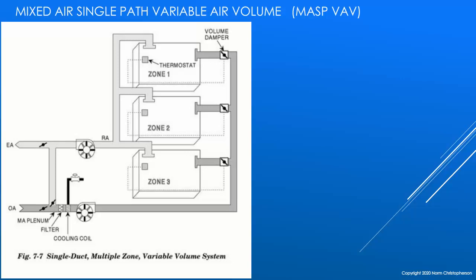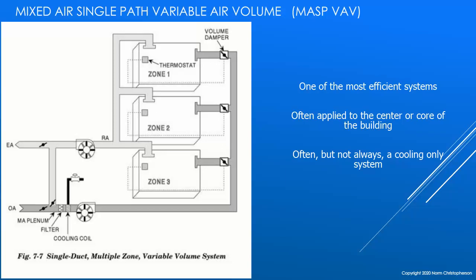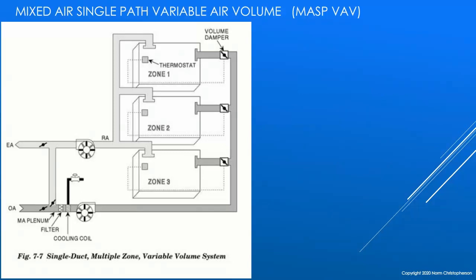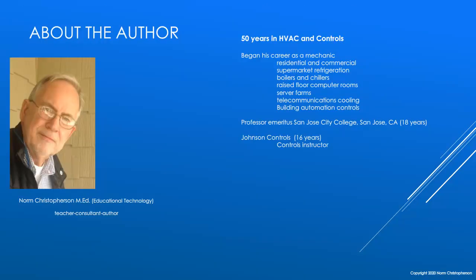Usually this variable air volume system serves the core — the center of a building — while a different system handles the perimeter. The core of the building usually needs cooling and not heating because it is self-heating: all the lights, people, computers, and equipment inside generate heat, and since the core is not near an outside wall, that heat builds up and requires cooling. That's the variable air volume system in a nutshell. That concludes Part 1. In Part 2, we're going to cover four more classifications of HVAC system types. Thanks for tuning in — this is Norm Christofferson, and I will see you again next time.